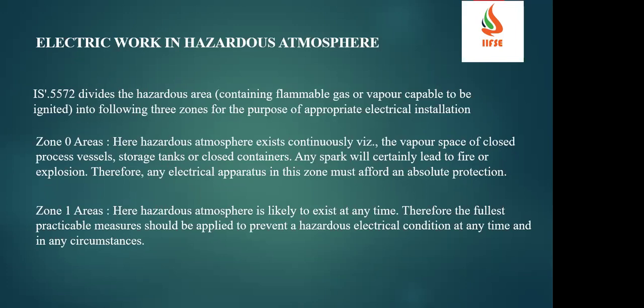Now let's see electric work in hazardous atmosphere. I think here itself we have covered this. There is an Indian standard, IS 5572, which divides the zone area or hazardous area classification. If you see zone 0, here the hazardous atmosphere exists continuously, in the vapor space of closed process vessels, storage tanks or closed containers. In the sense, the flammable atmosphere is continuously present in zone 0. And zone 1 is where the hazardous atmosphere is likely to exist at any time.